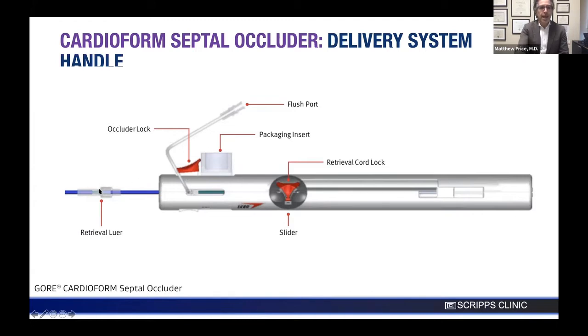There's a luer lock here. There's a delivery catheter which enters the delivery sheath. So this retrieval luer is going to come into play if you ever want, after you've locked the device, to get it back because you want to abort the procedure. It's very easy. You just loosen the luer lock and you pull the entire handle back into here, and that'll bring the device into the delivery sheath in a very straightforward fashion.